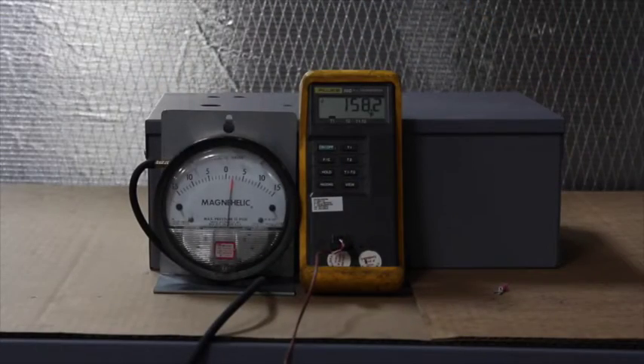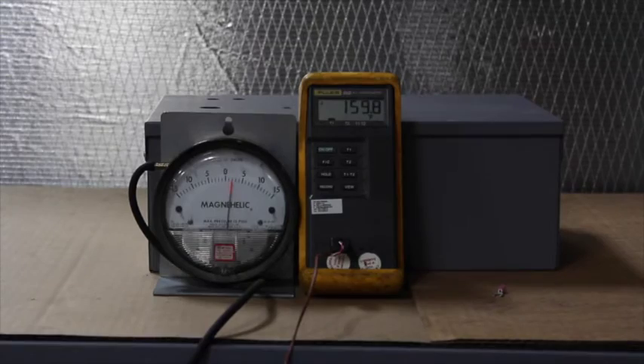Once you have calibrated your discharge sensor, monitor your discharge temperature. You are looking for between 155 and 160. If you exceed 160, recalibrate to below 160.